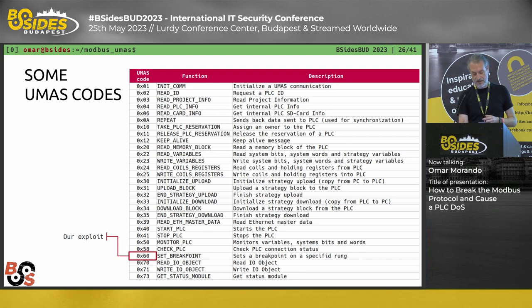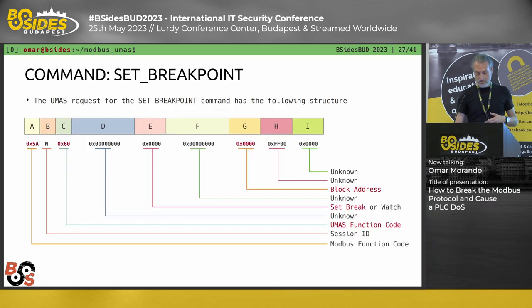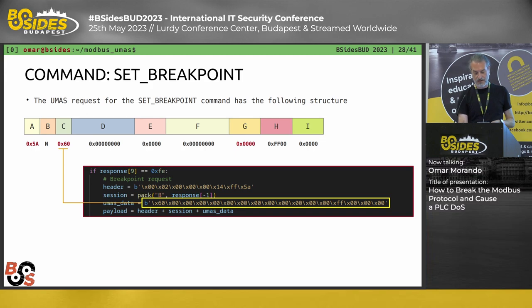One of these is the set breakpoint command, with the specific code 0x60. By crafting the breakpoint frame of the Modbus protocol using a very simple line of Python code, you can stop the PLC at a specific portion of memory, completely halting the PLC and also its Ethernet communication. This means the PLC stops running and becomes unreachable - you cannot reach it via Ethernet.